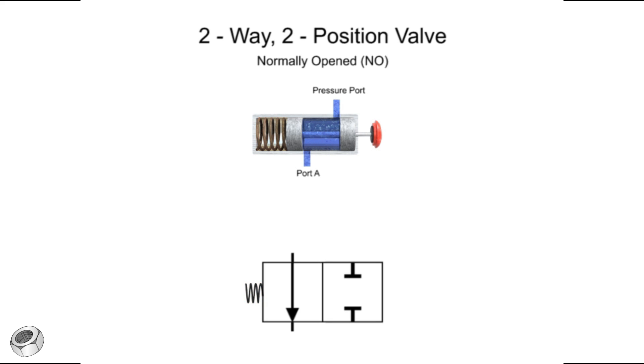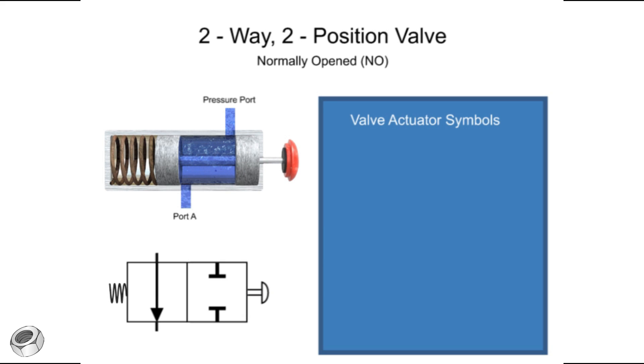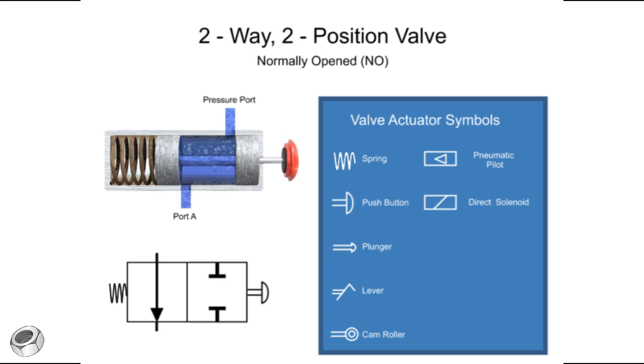Actuators used to change valve positions can be mechanical, pneumatic pilot, or electric solenoid. To complete the diagram, the primary actuator symbol is placed on the other end of the graphic symbol — in this case, the actuator is a push button. Mechanical actuators change valve positions with springs, push buttons, plungers, levers, and cam rollers. Pneumatic pilots change valve position with a pressurized air signal. Electric solenoids that directly move the valve element are called direct solenoids, while those that open small pilot valves and allow pressurized air to move the valve element are called solenoid controlled pilot operators.